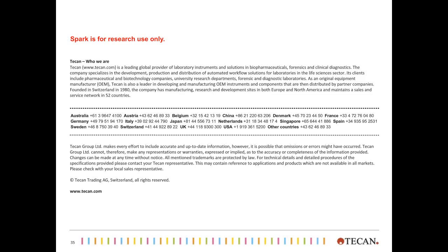It also somewhat depends on how old the instrument is, because over time dust can accumulate inside the instrument and prevent efficient ventilation. So a very old instrument will probably show higher temperature-related results variations than a brand new and modern reader. In addition, modern readers such as the Spark will have encapsulated measurement chambers that are better protected from ambient factors like light, temperature, and of course contamination. So they will be better suited for temperature-sensitive assays.